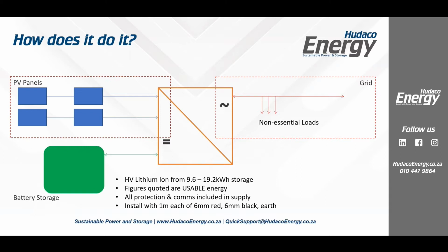We don't need to have all these other things, a whole DC box in between. It's literally the cables come out. The SUNCLIX connectors are provided in the box for you. So you put your SUNCLIX connectors on the red, on the black. The lugs are supplied in the box for your earth cable, both sides. And then you just earth that into the chassis.